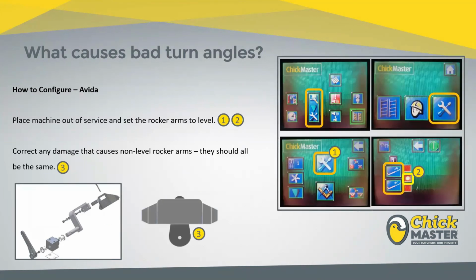Once you've got that turn height set, you put the turn system in level, and what you want to do is set that level limit switch so that the icon, which you can see in the bottom right hand corner here, is illuminated on the touchscreen. That tells you that the control system is aware and it's recognizing that limit switch in that middle position, that level position. Now, once it's set there, you want to manually drive the trolley away from that limit switch and then put the system back in level through the control. That'll get the PLC to drive it back to level, and what you may find is that it drifts ever so slightly away from that. So you want to adjust that level limit switch.